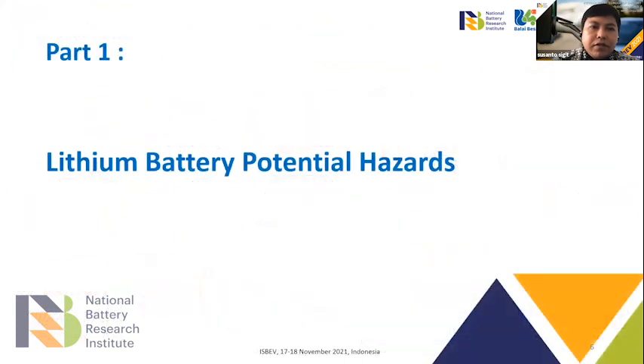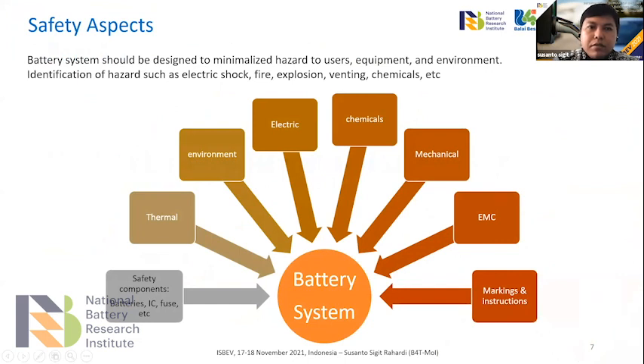Now we move to part one: lithium battery potential hazards. For safety, battery systems should be designed to minimize hazard to the user, equipment, and environment. Such hazards include thermal, shock, fire, explosion, venting, chemical, mechanical, electromagnetic compatibility issues, bad components such as battery, IC, fuse, and other safety components, and also misuse by users due to lack of education and knowledge of the product, or bad marking and inadequate instructions.